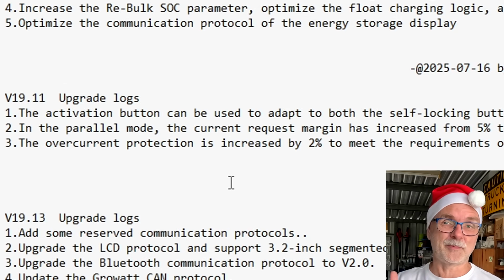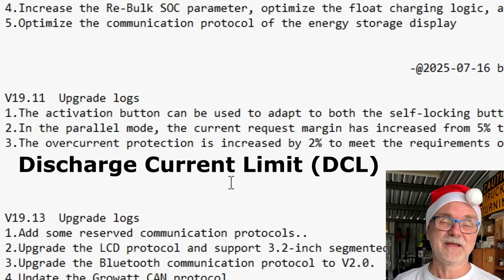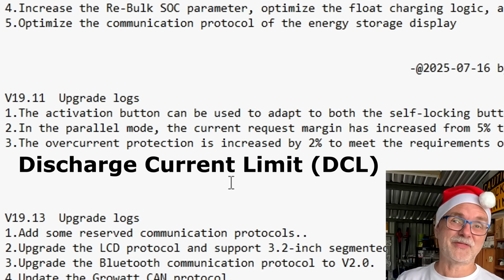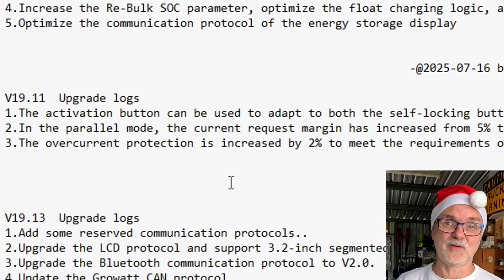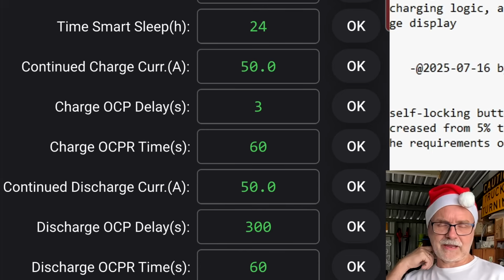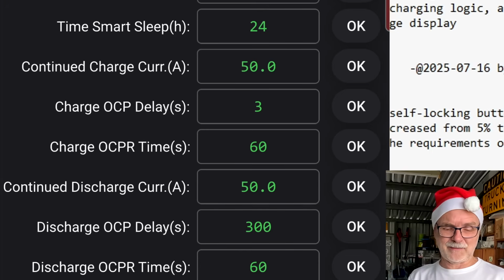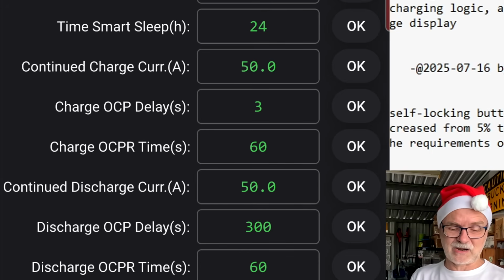This is the maximum charge current the BMS requests from your inverter to charge the battery. And number 3 is the opposite. It is about the DCL, the discharge current limit. So the BMS tells your inverter what the maximum discharge current for the battery is at the moment. Okay, and both can be set in the JK BMS with a continued charge current and a continued discharge current, yeah? Both of them are sitting on 50 amps.